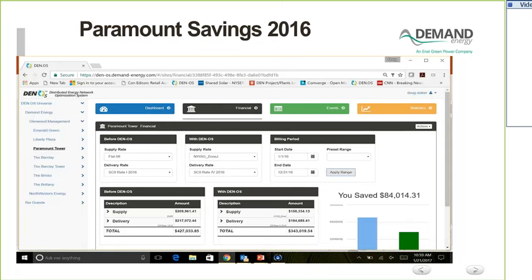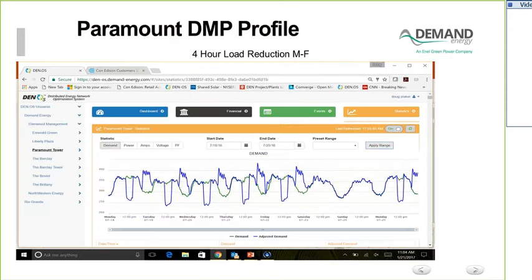What's impressive is that these systems were installed under the NYSERDA Con Ed DMP program. That means in the summer, June through September, we have to do a bulk generate from 2 p.m. to 6 p.m., where we run the system at full power and just reduce the load in bulk fashion. We don't follow the building load, we just inject.